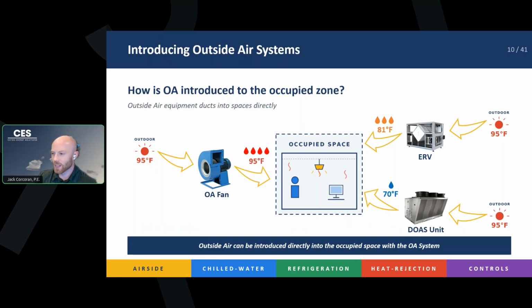And then lastly, your DOAS unit is bringing your 95-degree air down to space neutral. It is bringing it to 70-degree air that's not super moist or wet. It's just comfortable for the space as it needs. You can adjust; it doesn't have to be 70. It can be any temperature, based on the capacity of your DOAS unit. And so this is dumping it directly into the space. That's one way to do it.